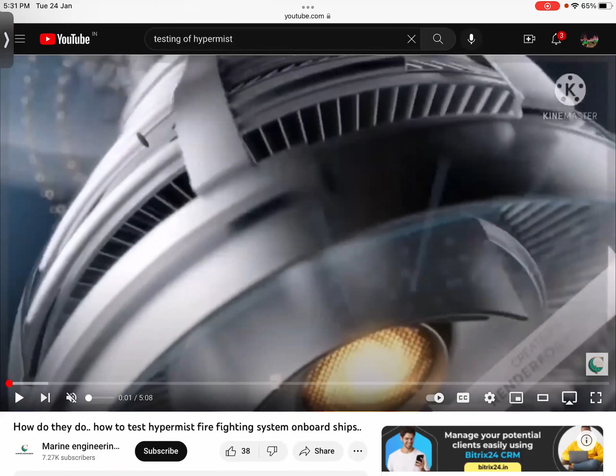In the meanwhile, I'll tell you about the SOLAS regulation. What does the SOLAS regulation say? Like I told you, a machinery space above 500 cubic meters of volume must have a local firefighting system. It must have a flow rate of 5 liters per minute per square meter, and it must also have a connection with the ESB, the emergency switchboard. It is a requirement for ships of more than 2000 GT.